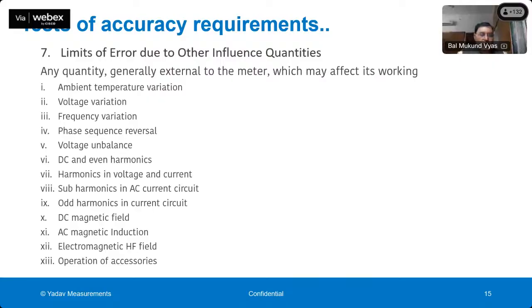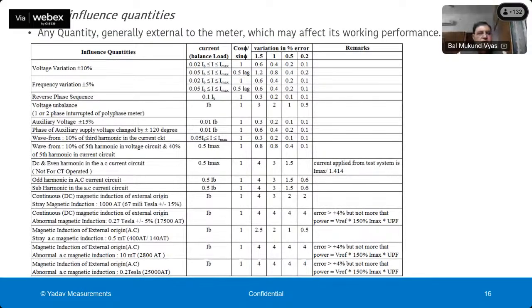Another is electromagnetic high frequency field, or EMI/EMC influences. Because we have high frequency fields almost everywhere, this is a very important test. The meter is kept under a high frequency field, and accuracy is tested, along with various accessories. So this table actually gives you, for all these influences, the error limit with respect to the reference condition, the variation in percentage error that is allowed because of all these influence quantities.